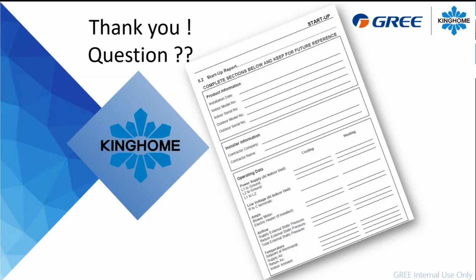So write down a maximum of information, especially from the startup, because back in the days, I remember sometimes the startup is bad, it's not a good installation, and it can run like this for over a year. Then you go back as a service guy and try to find out what's going on with the system. Is it a new problem or an old problem? By having a good startup report from the beginning, with the right information written down, this is very helpful for your company to provide quicker service and make everyone happy.